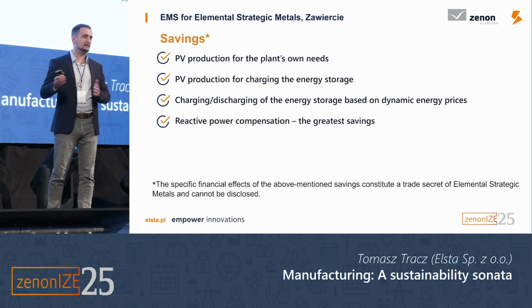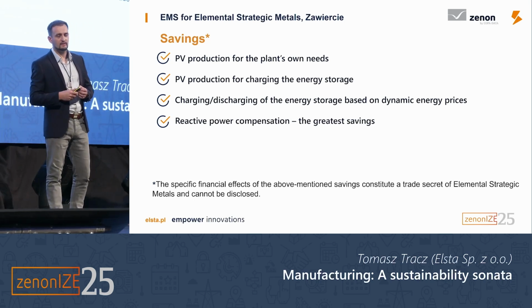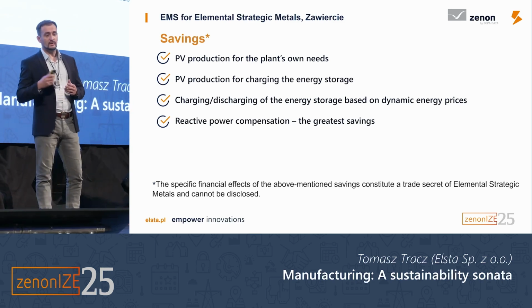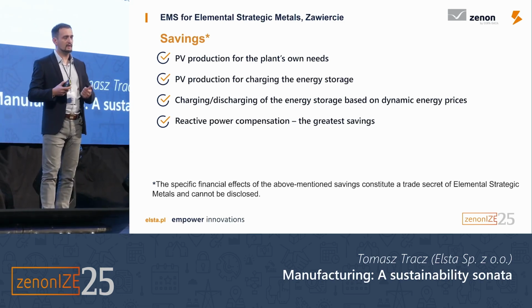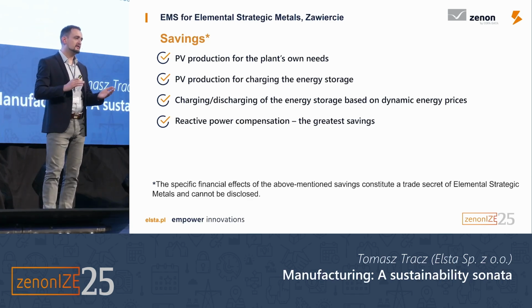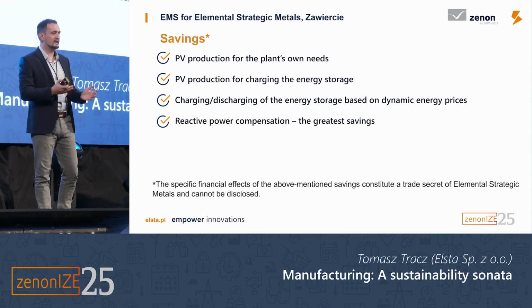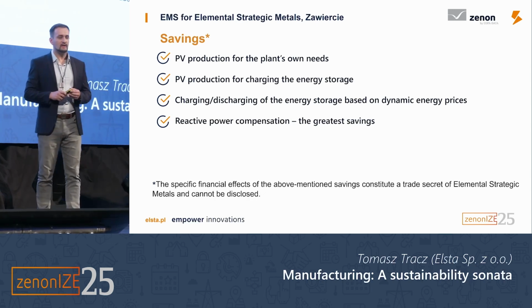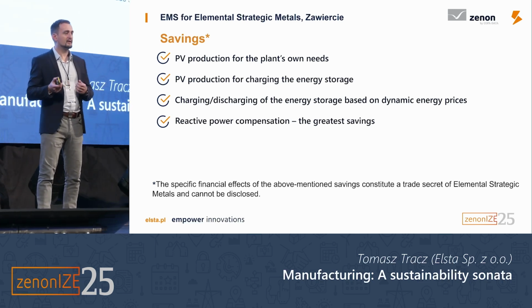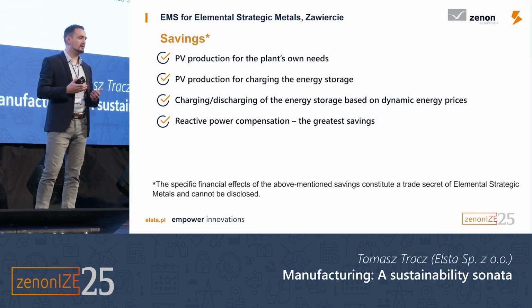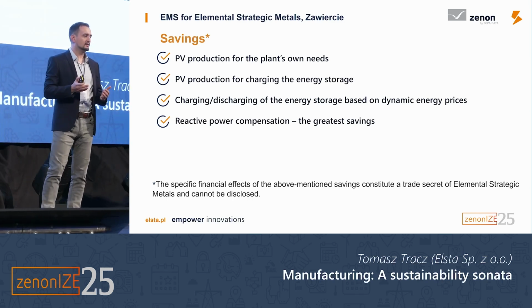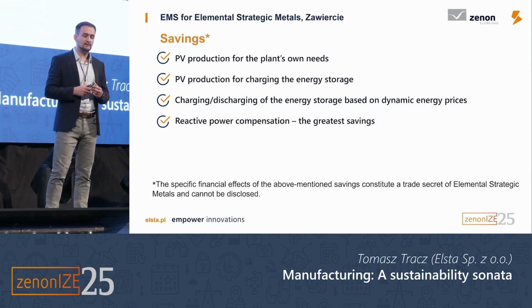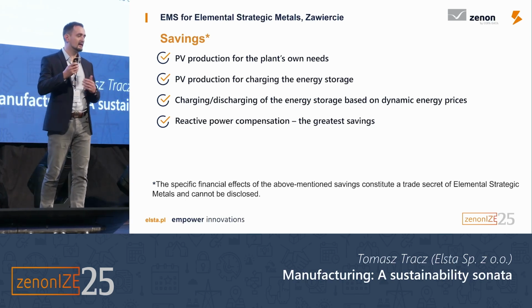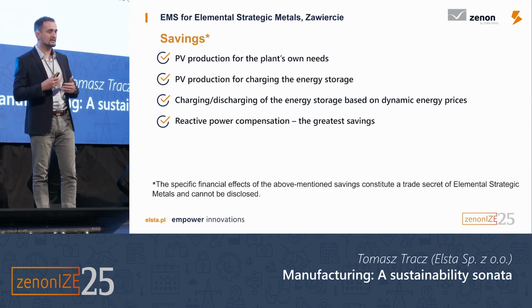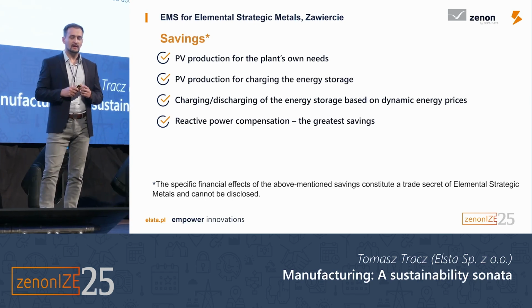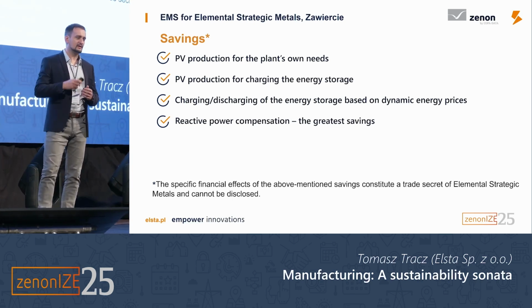As already said, it was 14 megawatt storage in the energy storage system. Now they want to double it at least, because they found out that not only production of PV is helping them, not only playing with the energy, which is currently quite limited because they cannot sell, they can just buy it and use it at the right time. But they also found out that they had a real issue with reactive power consumption, and due to the characteristic of the battery storage system, it was corrected a lot by default, I would say, and most of the savings which they achieved was just from this feature. They were quite surprised how their system was not optimized in this field, and the return on investment will be really, really quick.